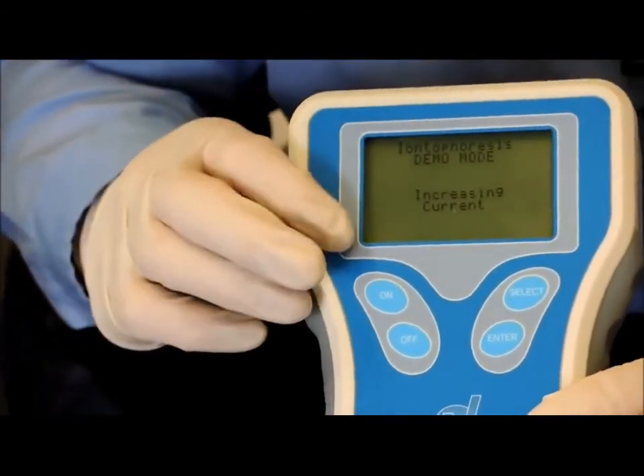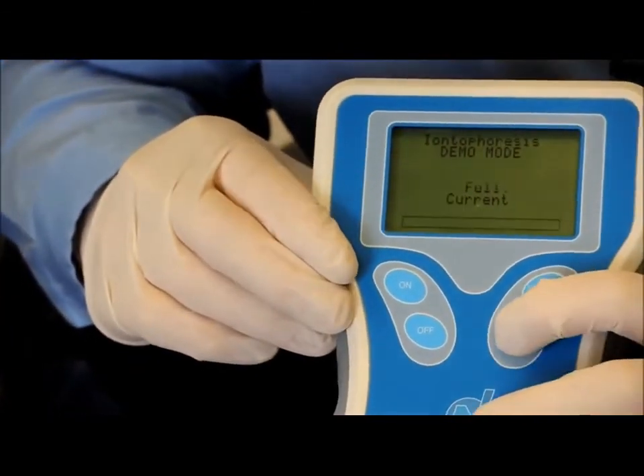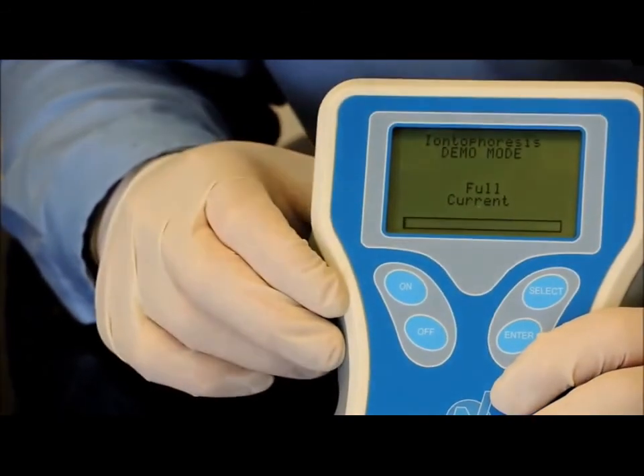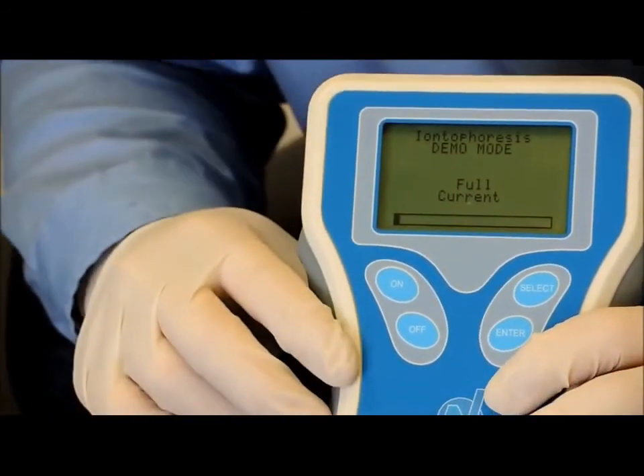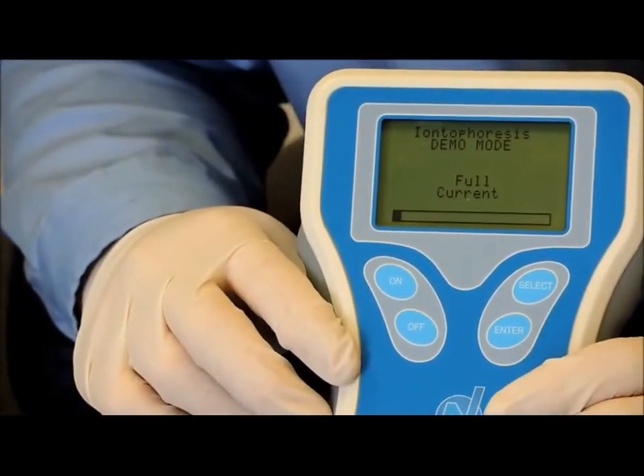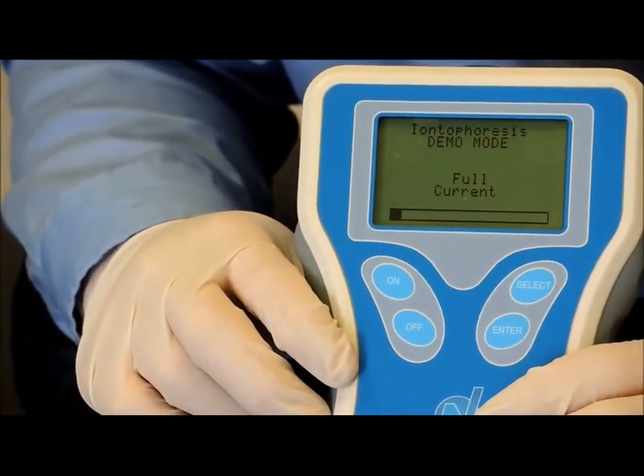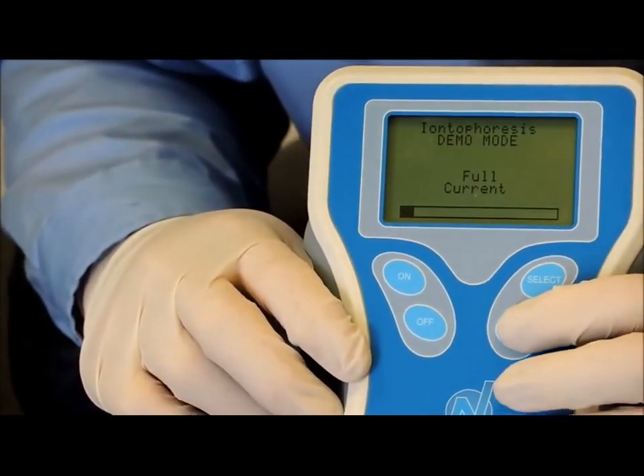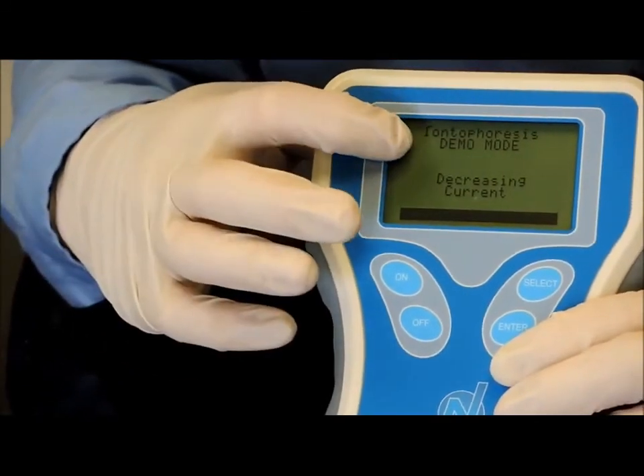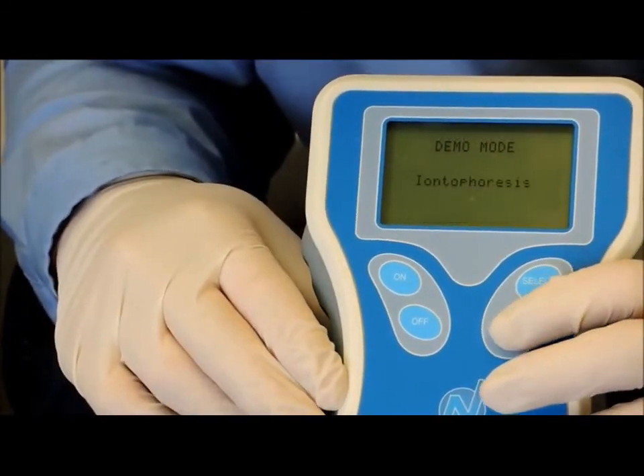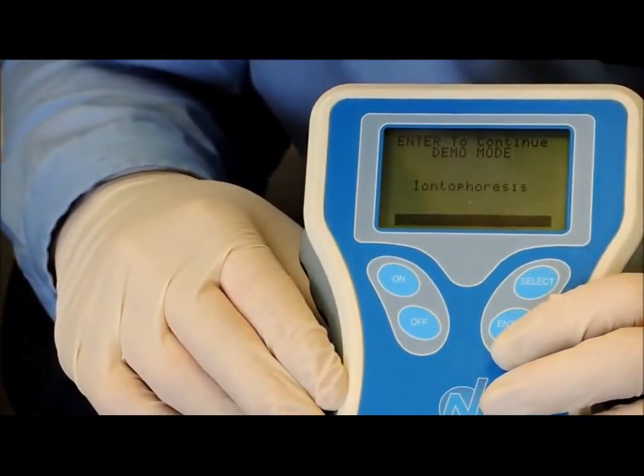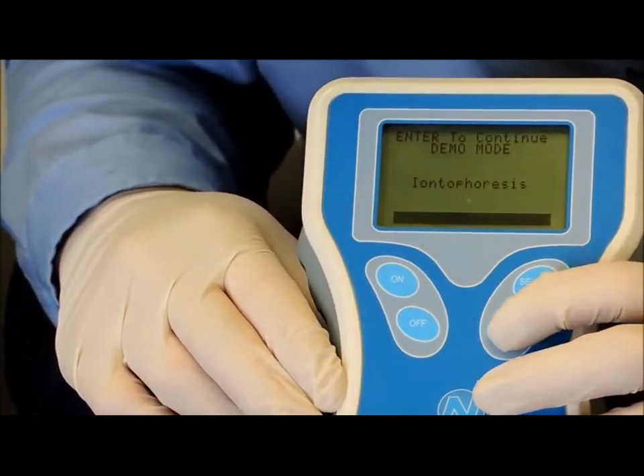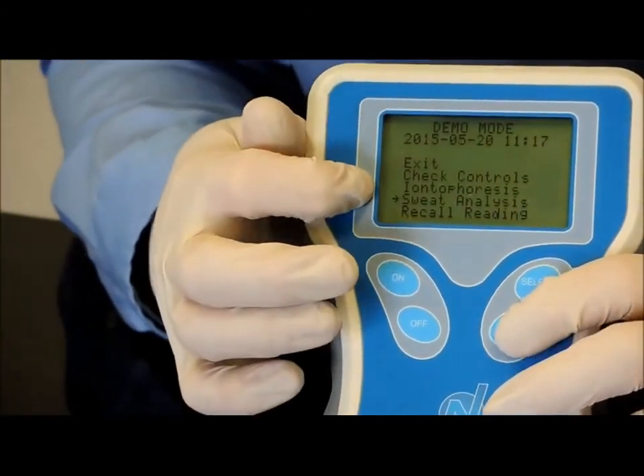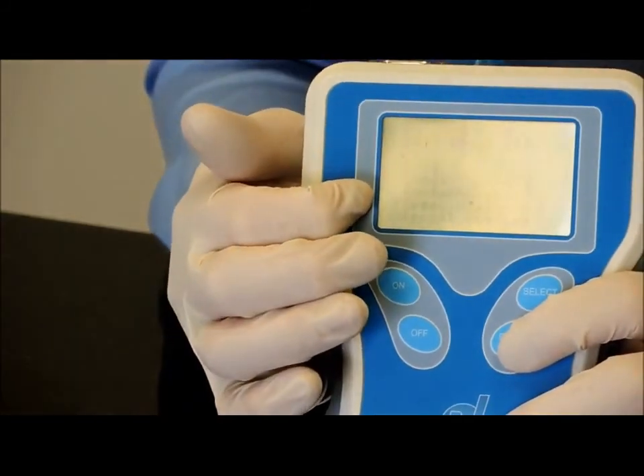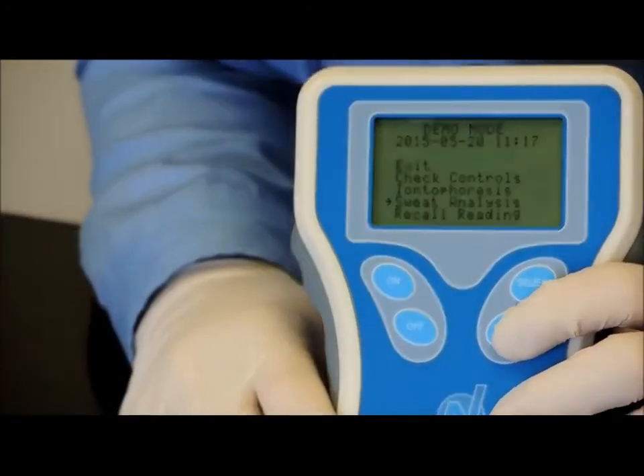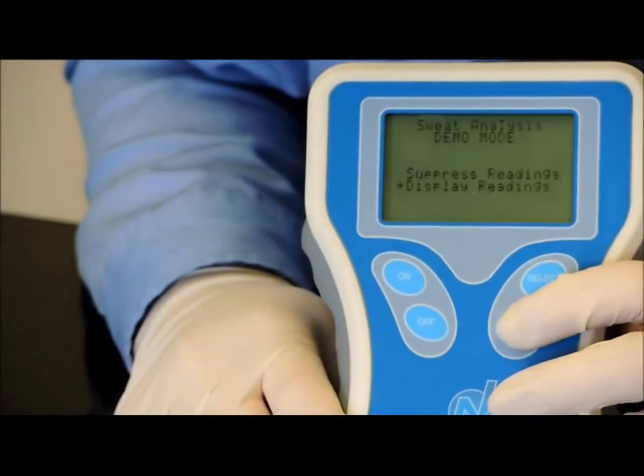So it does the increase in current. I can hit enter and it skips ahead to full current, and with the progress bar. Again, that would take 2.5 minutes, but if someone doesn't want to take a lot of time, you can hit enter again, and it goes to decreasing current. And enter again, it says iontophoresis is complete. Enter again. Now the arrow is down at sweat analysis, and so we can enter into there.